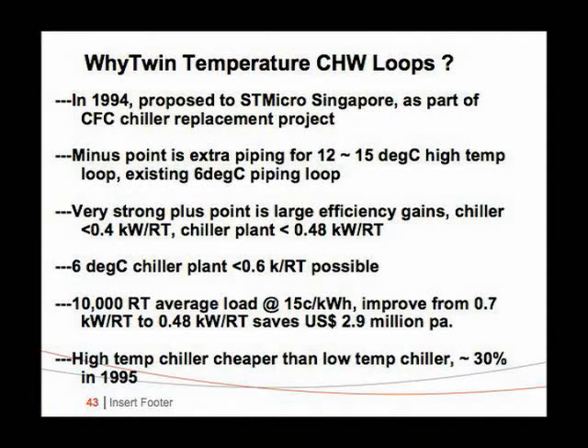So if you take a typical fab with 10,000 ton average load, there are sites with 250,000 tons, so 10,000 is not a large site. At 15 cents, going from a normal 0.7 to 0.48 will save 2.9, so the payback is typically in the order of 1 year or less, because you have now downsized your electrical requirements, which are quite extensive. And of course, your high temperature machine, at the time we installed it, was 30% cheaper for the same tonnage.